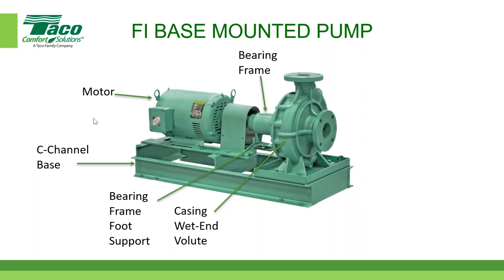The motor frames that fit this base include a 254 and 256 frame directly on the plate, a 184 and 182 frame with a spacer, and a 143/145 frame with two spacers, as the H-dimension height decreases for smaller frames. We also have a coupler guard as standard, and an OSHA coupler guard is available as an option.